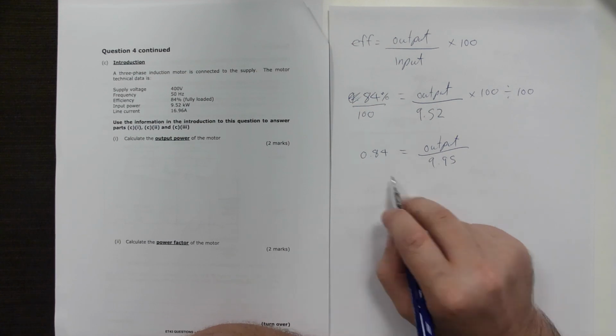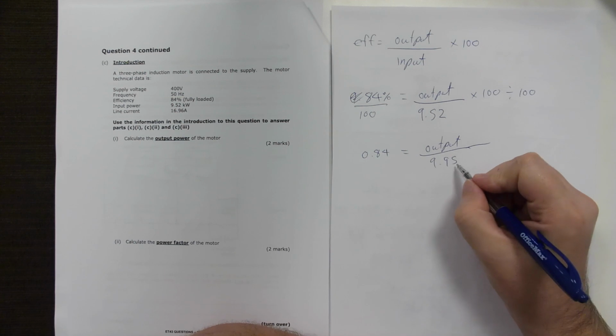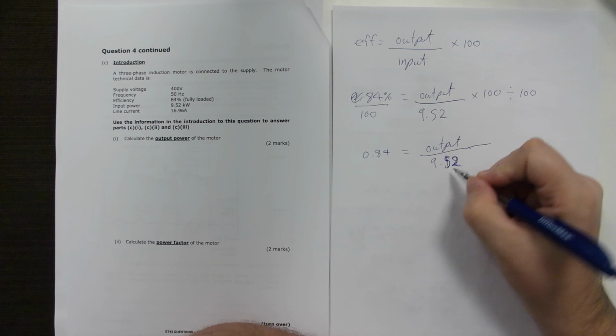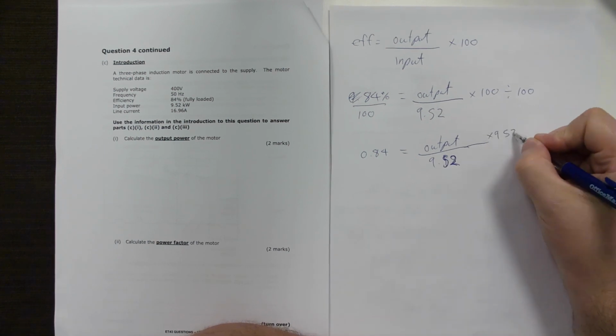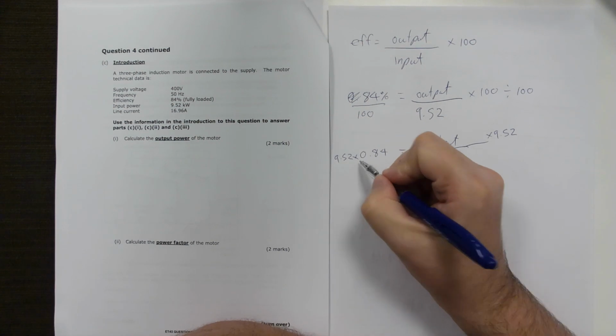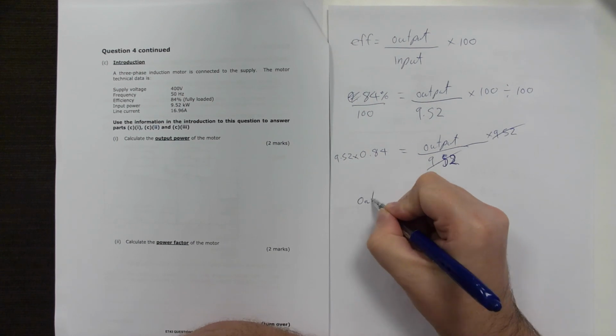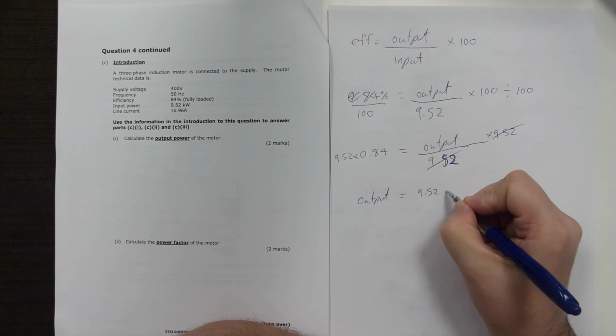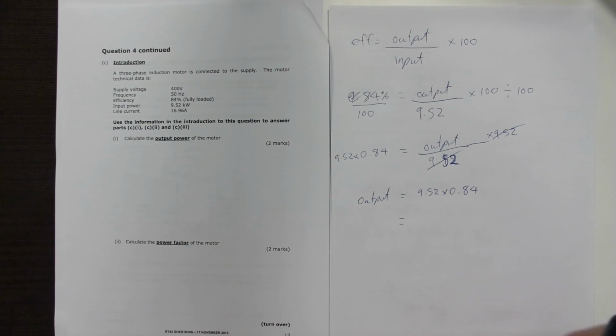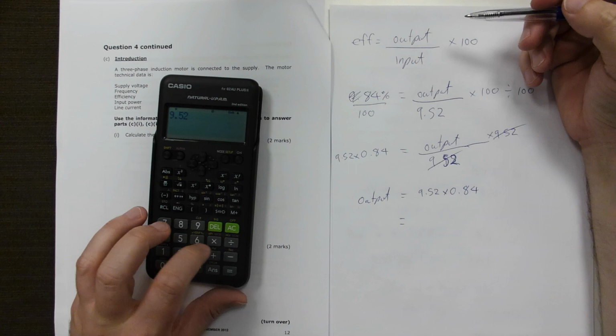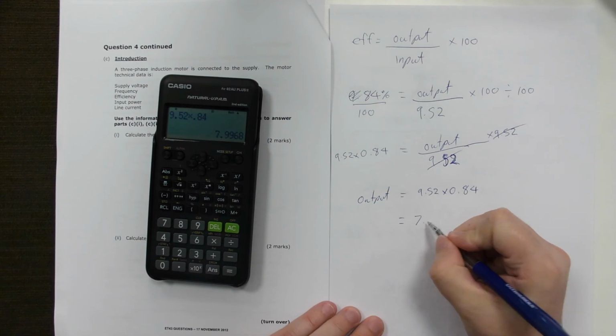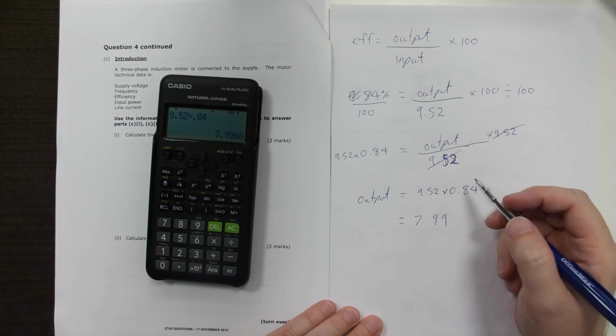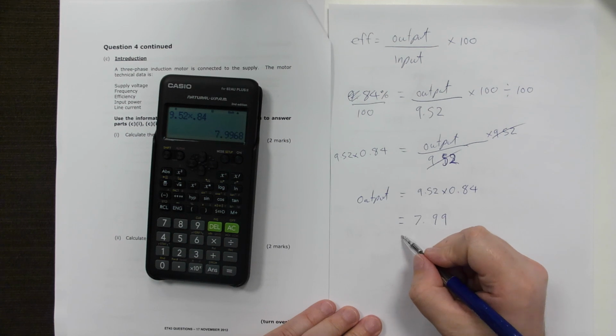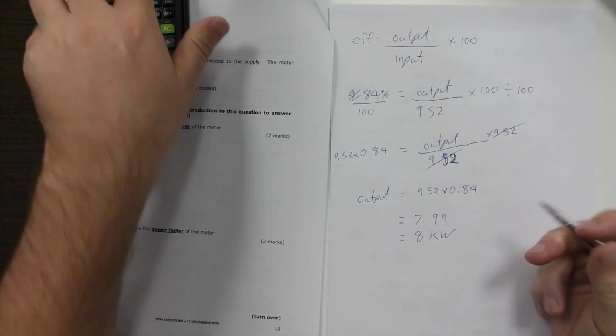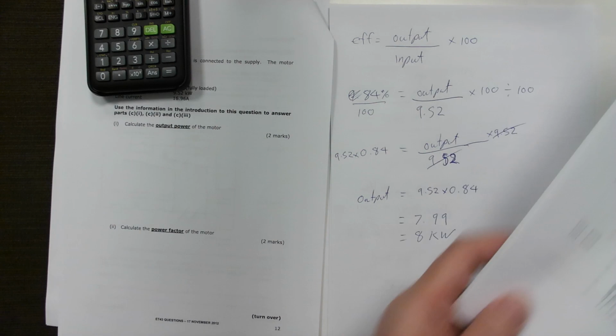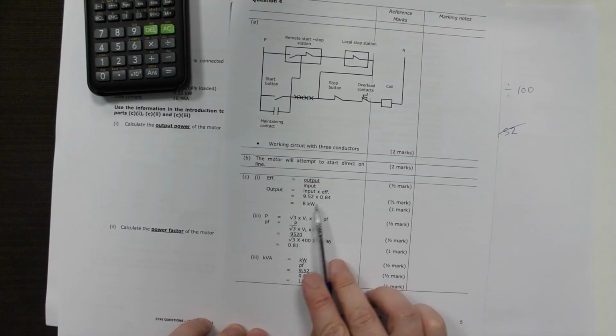So now we rearrange this so that it's output equals. So what we do is we are currently dividing by 9.52, so we need to multiply by 9.52, and then we have to do that on the other side, 9.52 times. These 9.52 cancel, so we end up with output equals 9.52 times by 0.84. If we put that in a calculator, 9.52 times by 0.84, we get 7.9968. Rounding this to two decimal places anyway, equals 8 kilowatts. And if we go to our answer sheet, our answer sheet says 9.52 times 0.84 equals 8 kilowatts.